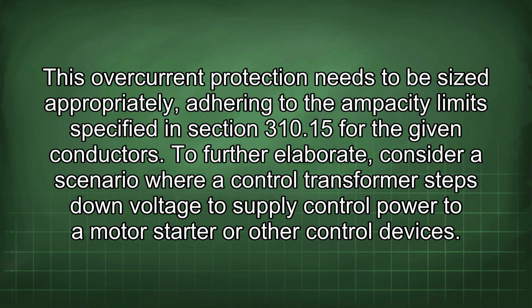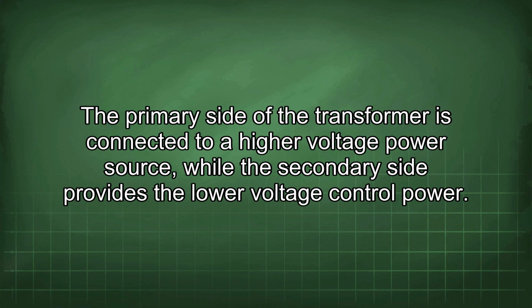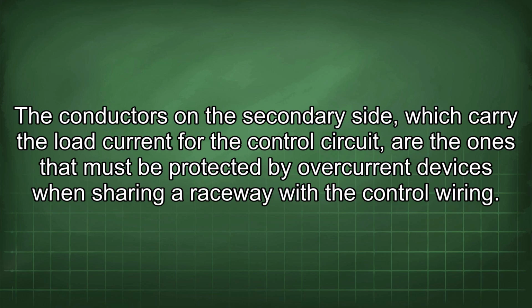To further elaborate, consider a scenario where a control transformer steps down voltage to supply control power to a motor starter or other control devices. The primary side of the transformer is connected to a higher voltage power source, while the secondary side provides a lower voltage control power. The conductors on the secondary side, which carry the load current for the control circuit, are the ones that must be protected by overcurrent devices when sharing a raceway with control wiring.